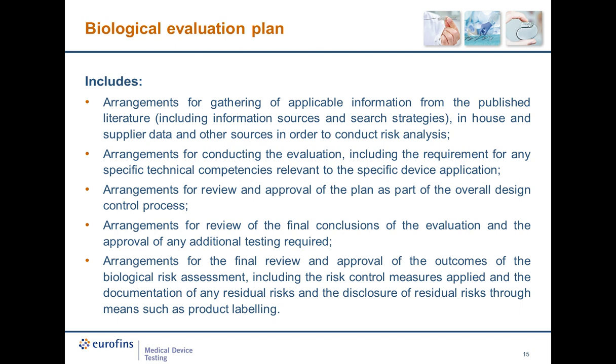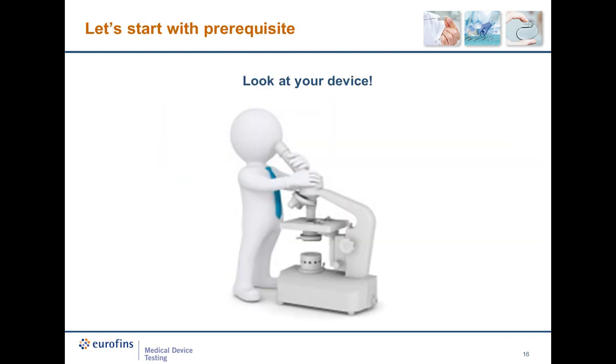The biological evaluation plan includes arrangement for gathering information, arrangement for conducting the evaluation, including the requirements of any specific technical competences relevant to the technical device, arrangement for review and approval of the plan as a part of the overall design control process, arrangement for review of the final conclusion of the evaluation and the approval of any additional testing required, arrangement for the final review and approval of the outcomes of the biological risk assessment, including the risk control measures.